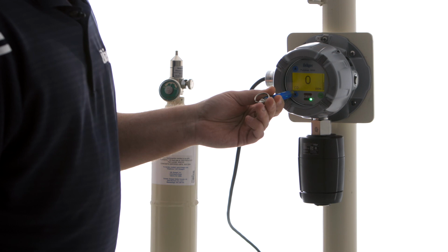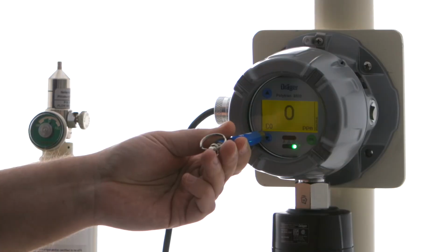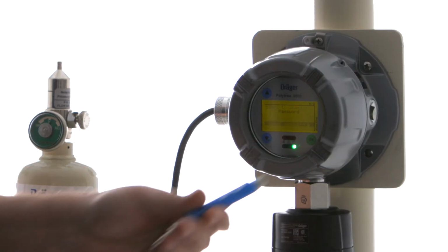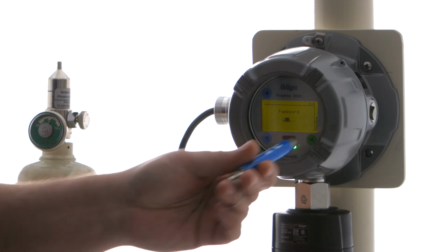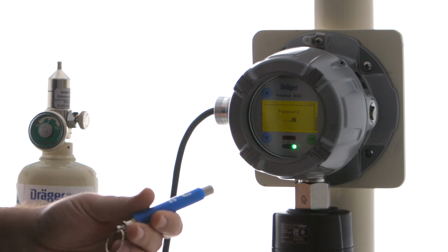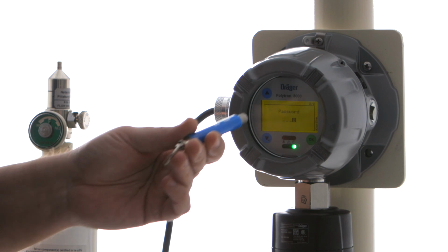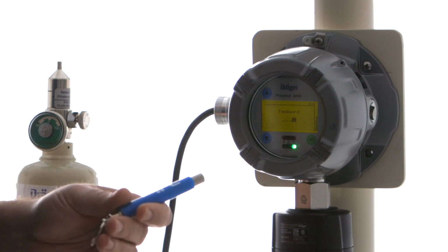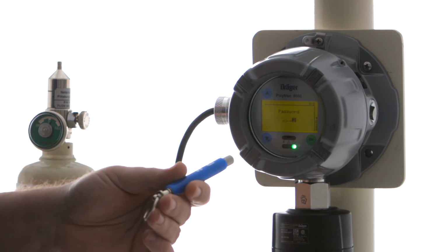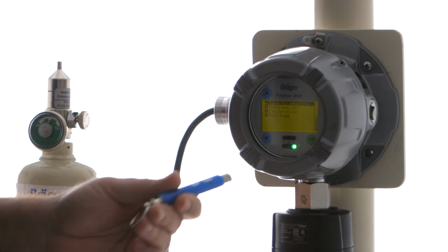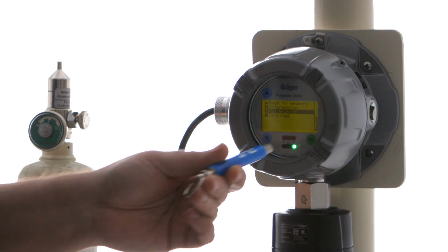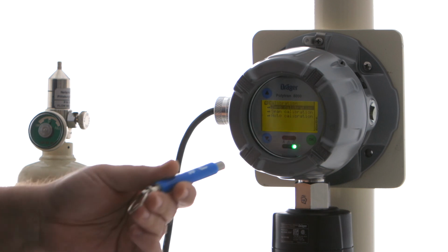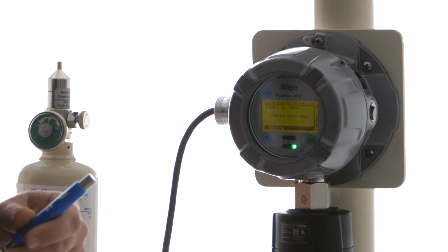So we have to get into the menu. We're going to press and hold the down arrow, enter our password. You can enter either password of 1 or 2. 1 will allow you to do the calibration, 2 allows you to do the entire configuration of the device. I'm just going to choose 2. We're going to go to calibration, and we're going to perform a zero calibration.